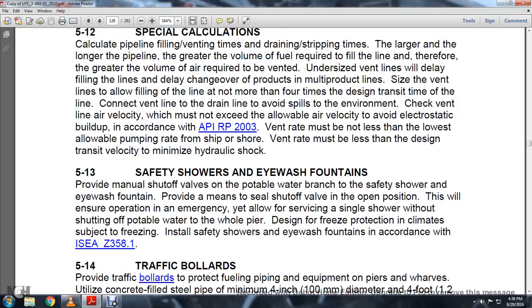513 safety showers and eye wash fountains. Provide a manual shutoff valve at the potable water branch of the safety shower. For the eye wash fountains, provide a means to seal the shutoff valve in the open position. This will ensure the operation of the emergency equipment, yet allow the servicing of a single shower without shutting off potable water to the whole pier. Design for freezing protection in climates subject to freezing. Install safety showers and eye wash fountains in accordance with ISEA Z358.1.